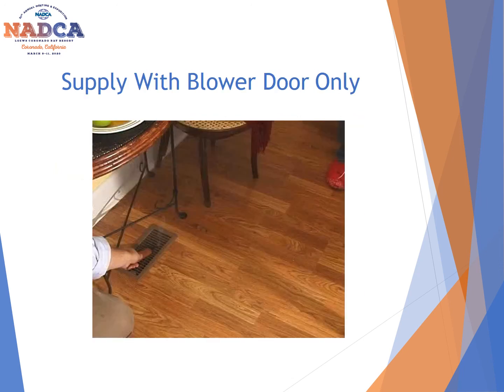And again, if your system is turned off when you're utilizing this, and you go to a register, for example, this one, a floor register, and you hold smoke up to it and you see airflow, well, that tells you that you have a leak in the system somewhere, and you're actually pulling air through the ductwork, which you shouldn't be able to do if the system is sealed tightly. So this is signifying that you have a leak somewhere near this actual register, which will help you identify where you need to go and basically seal those leaks and make sure that it is sealed properly.